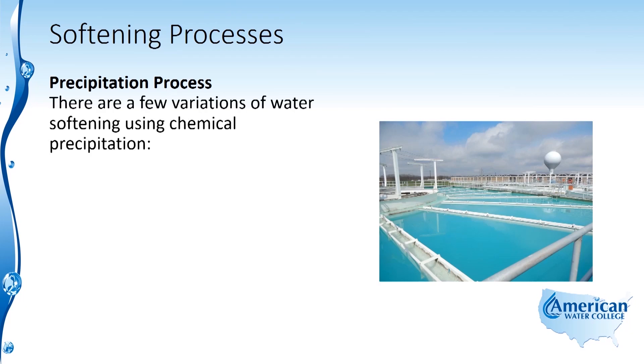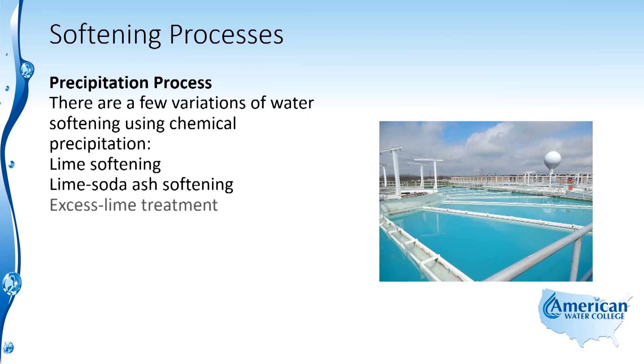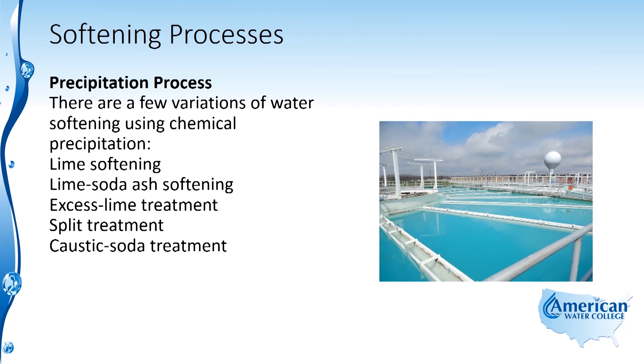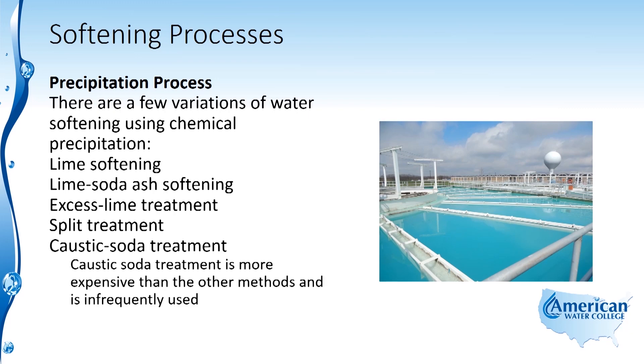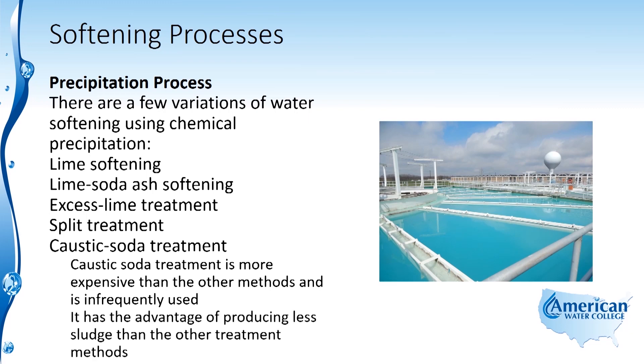There are a few variations of water softening using the chemical precipitation process: lime softening, lime soda ash softening, excess lime treatment (used to remove larger quantities of magnesium), split treatment, and caustic soda treatment. Caustic soda treatment is more expensive and infrequently used, so it won't be discussed further. However, it does have the advantage of producing less sludge than the other treatment methods.